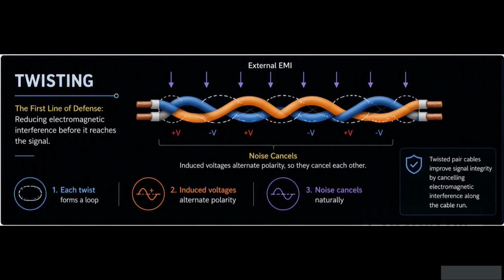When external electromagnetic interference passes through the cable, it induces a voltage in that loop. However, because the direction of the loop alternates with every twist, the induced voltages tend to cancel each other out. This significantly reduces the overall effect of external EMI on the signal conductors. This principle is particularly valuable for instrumentation and communication circuits that carry small electrical signals. By reducing noise pickup, twisted pair cables help ensure that transmitted information remains accurate and reliable.